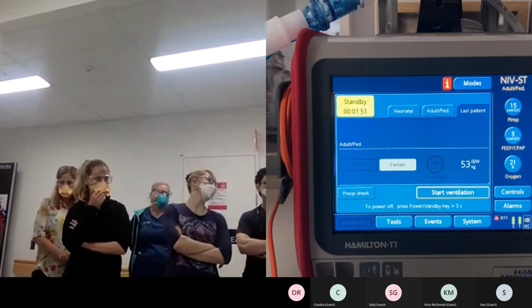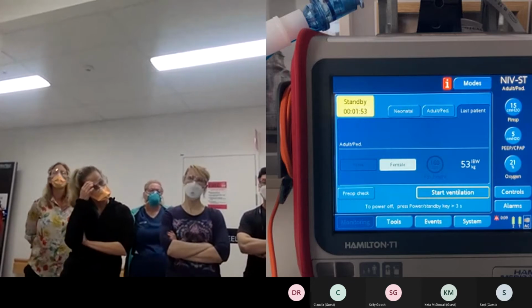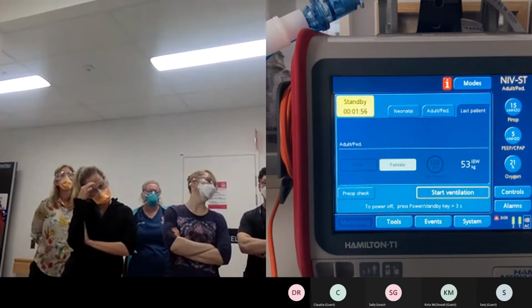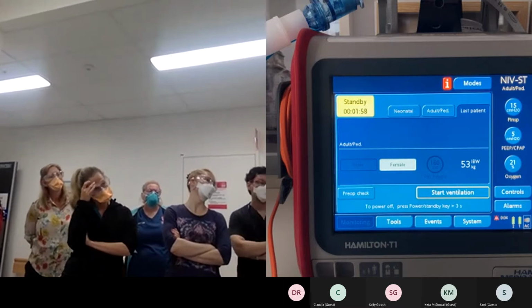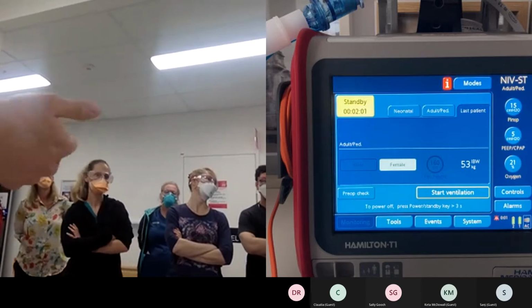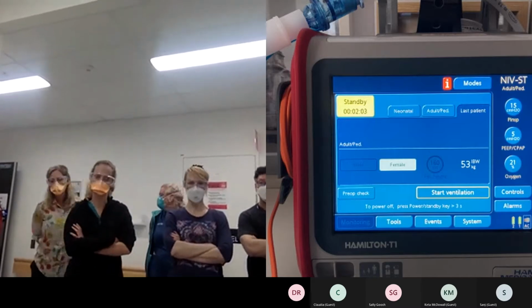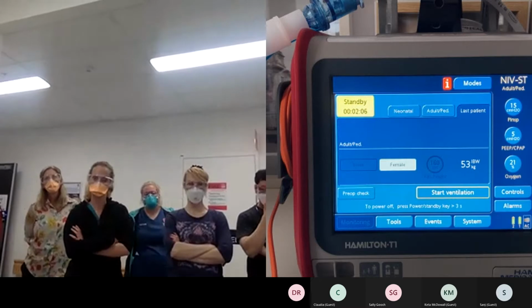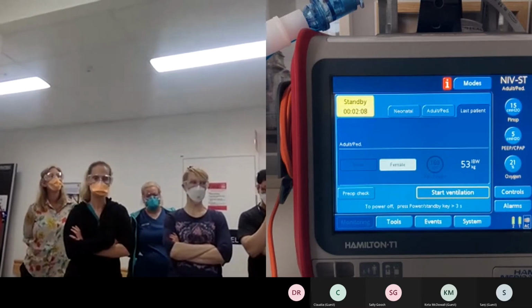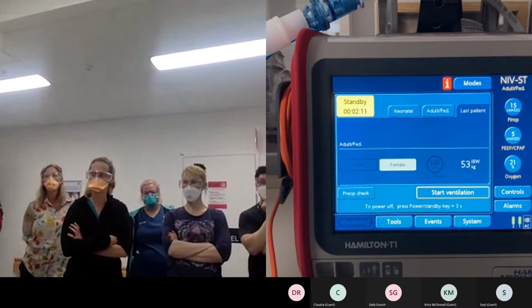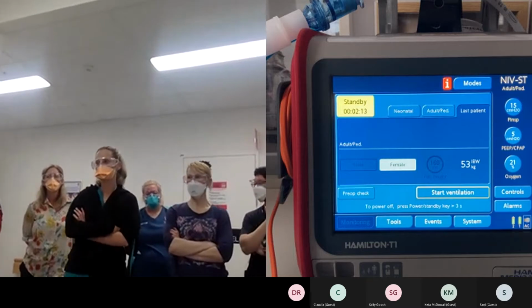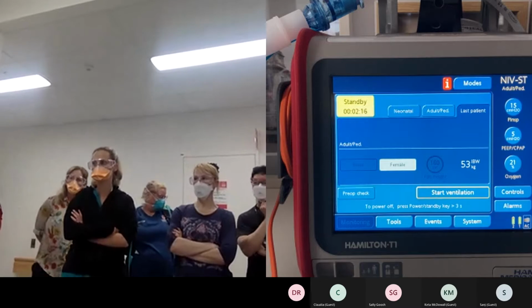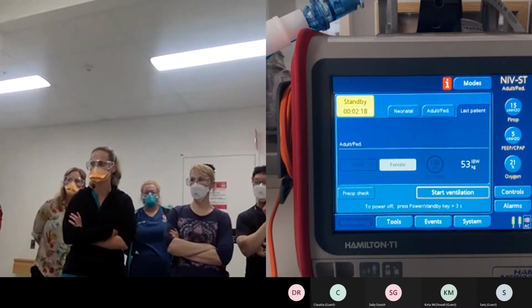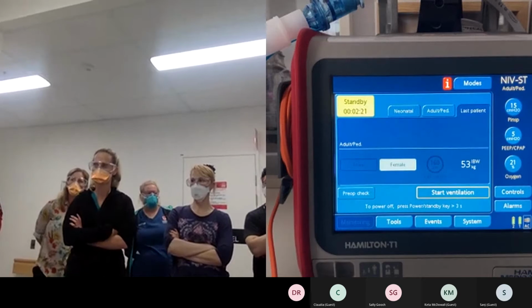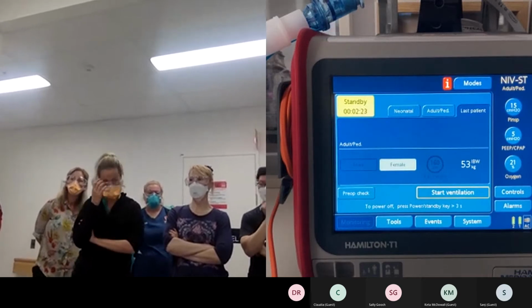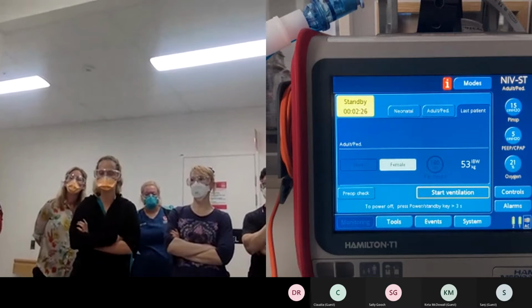So NIVST is what we're using as BiPAP, correct? Yes, with the mandatory backup rate. And then if we're making it CPAP, we turn our pressure support down to 0. Exactly, correct. You can't do CPAP in NIVST. No, we wouldn't be in that mode. It'd be in the CPAP mode. Yeah, go back to modes. So if you want a CPAP of 5, it would be 5 and then 0 pressure support.